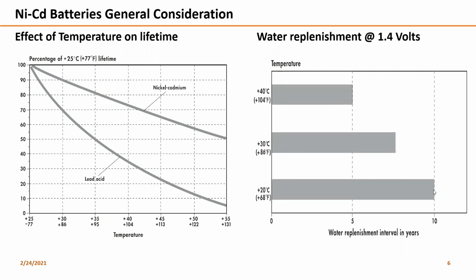As I said, there is no maintenance required for nickel cadmium at regular intervals. We may need to fill or add water to the batteries if it operates at 40 degrees C, maybe every 5 years. At the specific temperature of 20 degrees, we don't need any maintenance till 10 years. This is a major advantage, where we don't need people monitoring or maintaining the batteries. It gave an advantage over lead acid, and now everyone turns towards nickel cadmium batteries.